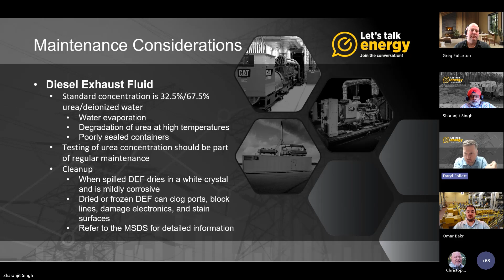It can quite easily clog ports, disrupt sensors, and plug lines when it dries, meaning that when the generator is called to run days, weeks, or months later, the DEF won't flow because you've got dried crystallized urea in critical areas. It can also damage electronics, so if there's a larger spill around the control system, it's a challenge that should be addressed right away.